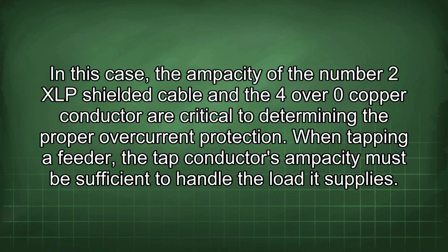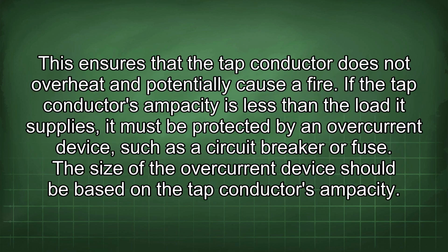When tapping a feeder, the tap conductor's ampacity must be sufficient to handle the load it supplies. This ensures that the tap conductor does not overheat and potentially cause a fire. If the tap conductor's ampacity is less than the load it supplies, it must be protected by an overcurrent device, such as a circuit breaker or fuse. The size of the overcurrent device should be based on the tap conductor's ampacity.